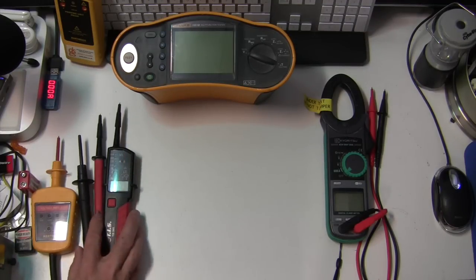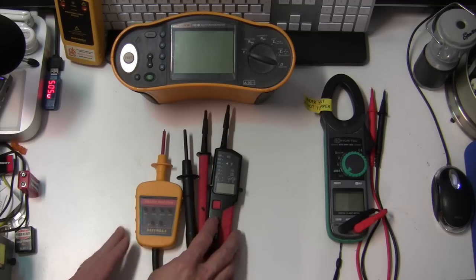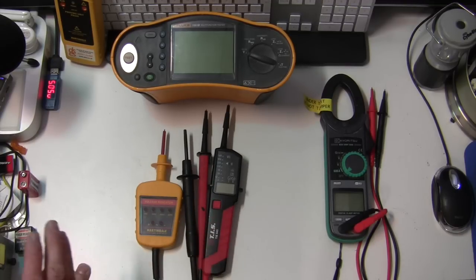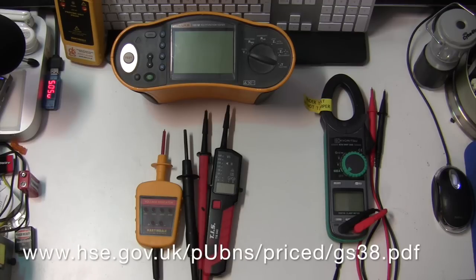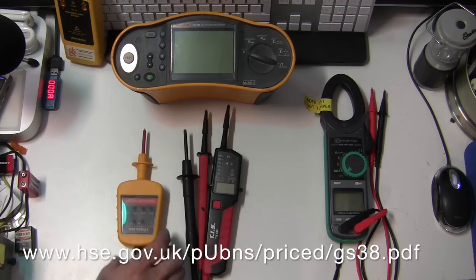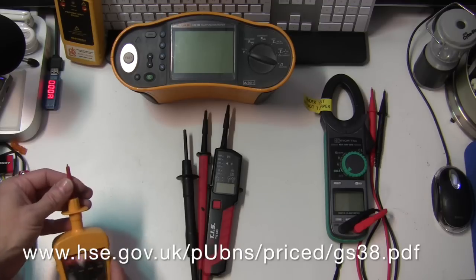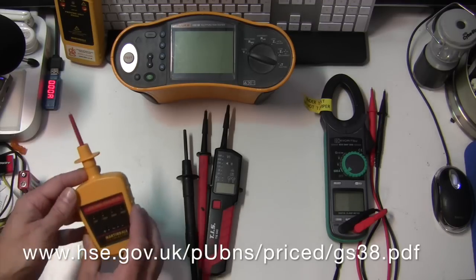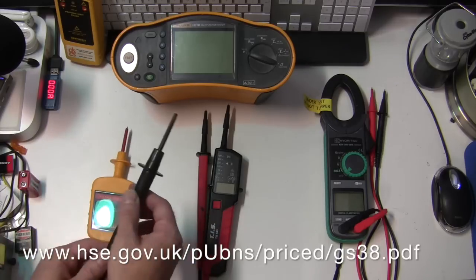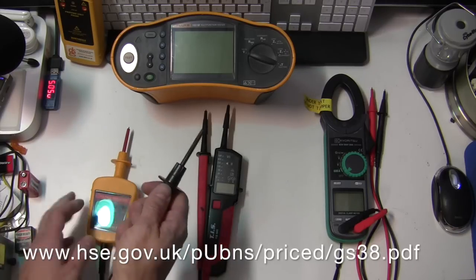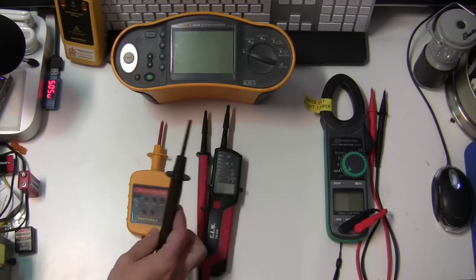You need a dedicated GS38 compliant voltage indicator. If you're not familiar with GS38, it can be downloaded from the HSE website. A couple of key points are that probe tips should be no greater than 4mm, with 2mm preferable, and that there are finger guards to prevent you slipping down the probe once you're pushing it into live parts.